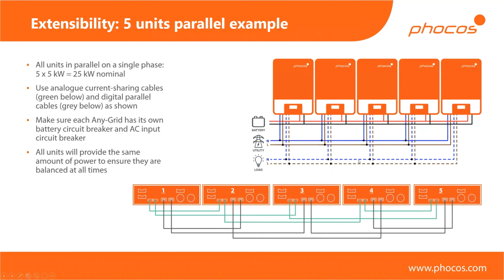So what this means, I have a few examples for you here. If we set up 5 AnyGrids on a single phase, then we need the green cables and the gray cables, because again, as soon as we have more than one unit on a phase, we will need the green cables. So that's what we have here. And either way, we definitely need the communication cables between the units where we synchronize all the settings, where if there's a phase shift, if you're using a three-phase system, that's where the information travels for the phase shift, etc.